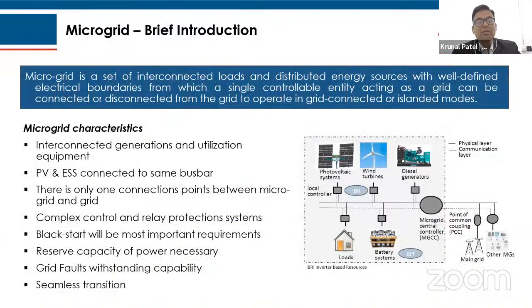So from here I wanted to start covering my technical topics, and for that, in the first slide, I wanted to introduce the microgrid. As we all know, a microgrid is a set of interconnected loads and distributed energy sources with well-defined electrical boundaries, acting as a single controllable entity that can be connected to or disconnected from the grid. In this diagram you can see multiple IBRs connected.